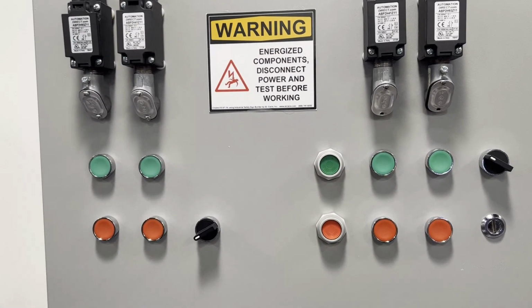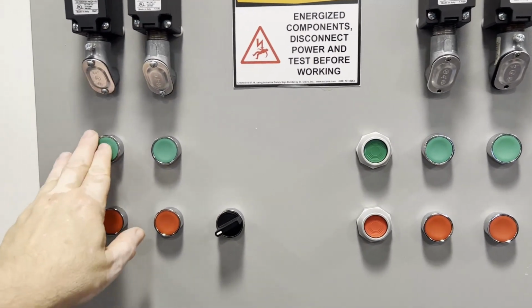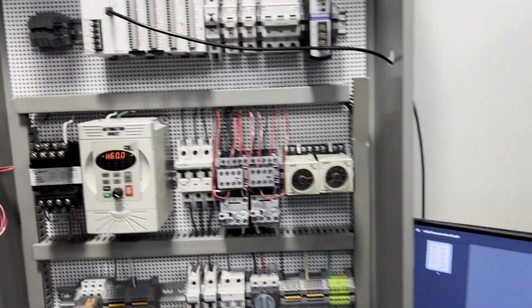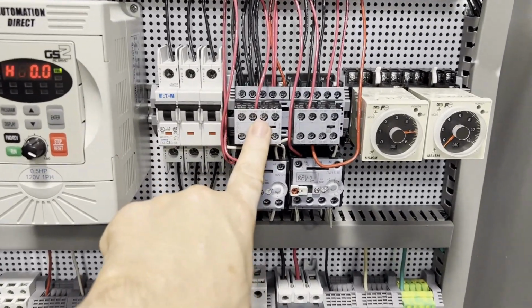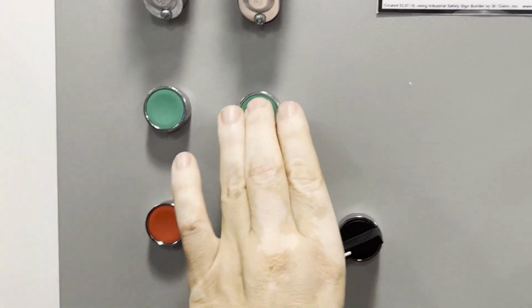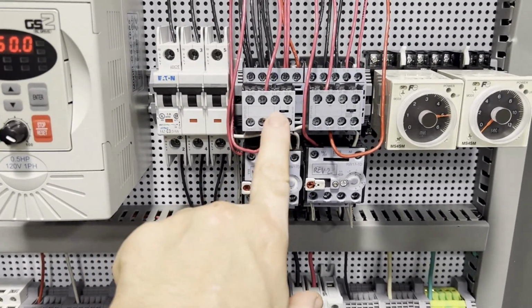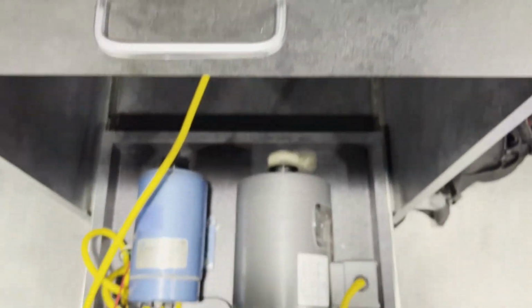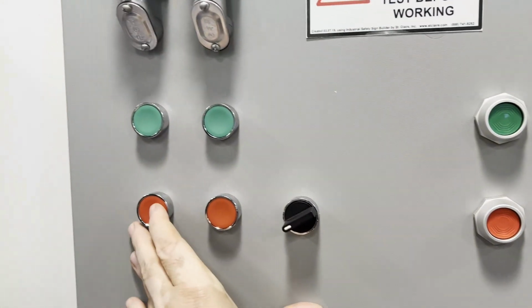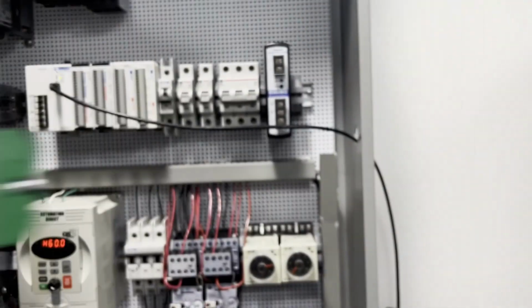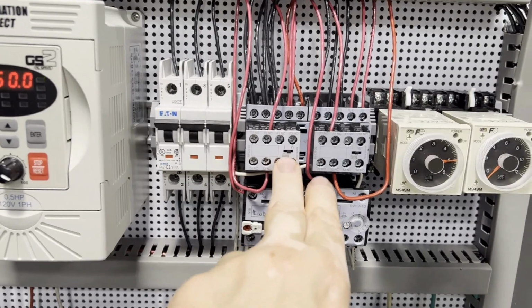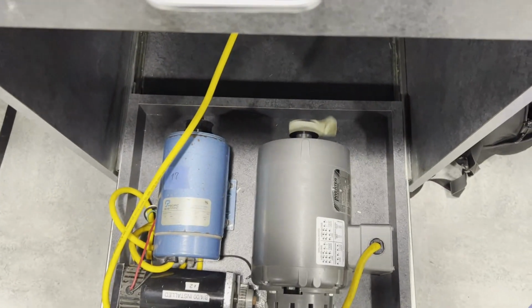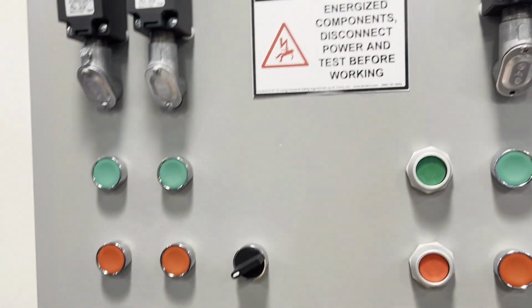Test number 7, forward interlocks. Start out pushing the forward button. Verify forward contactor. Motor turning in the forward direction. We push the reverse button. Did not hear any change in the sound. Verify. Forward contactor still closed. Reverse contactor still open. Motor still turning in the forward direction. Push the stop. And forward contactor open. And motor coasting down to a stop. This concludes the forward interlocks test.